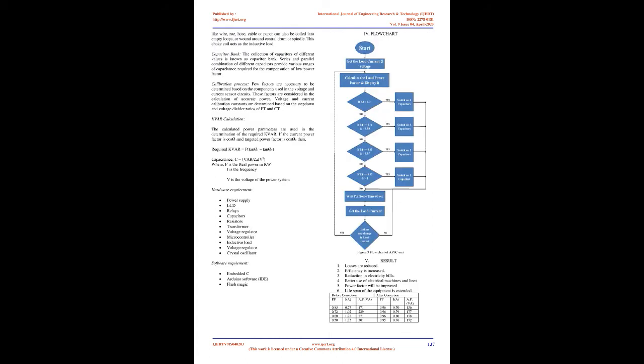Power factor correction. Capacitive power factor correction is applied to the circuits that include induction motors for reducing the inductive component of current and thereby reduces the losses in the supply. There should be no effect on the operation of the motor.